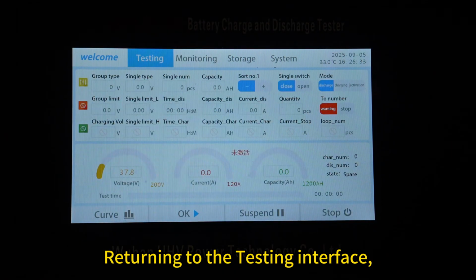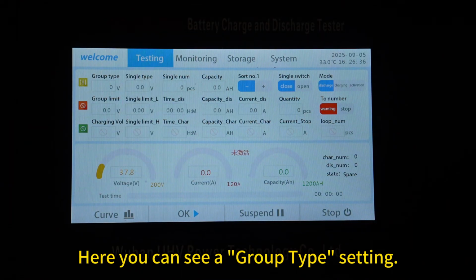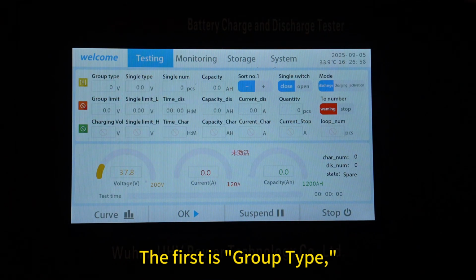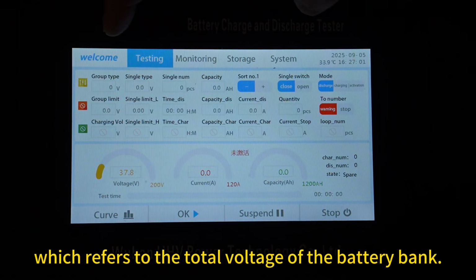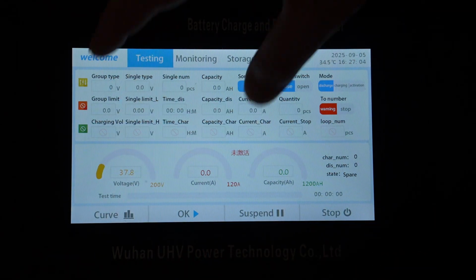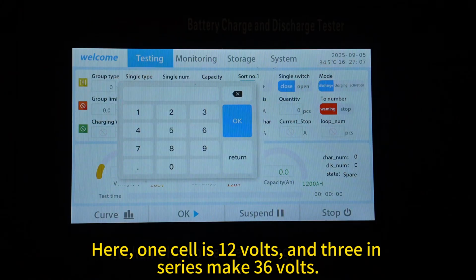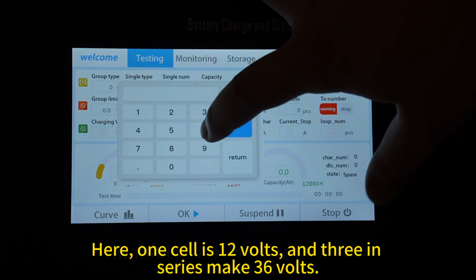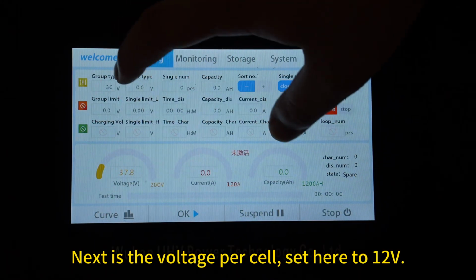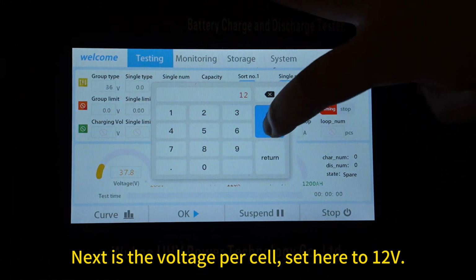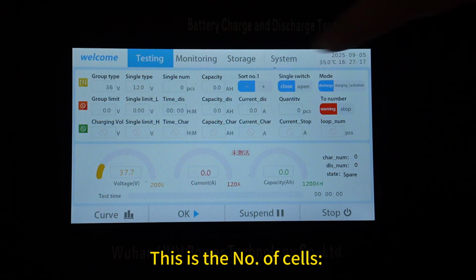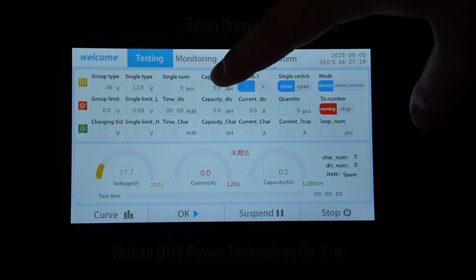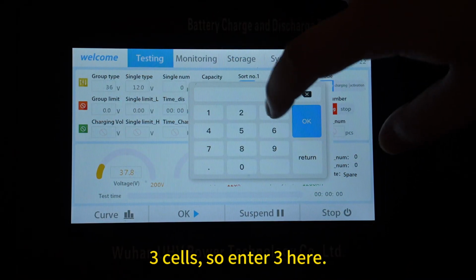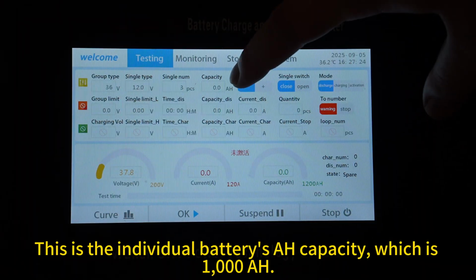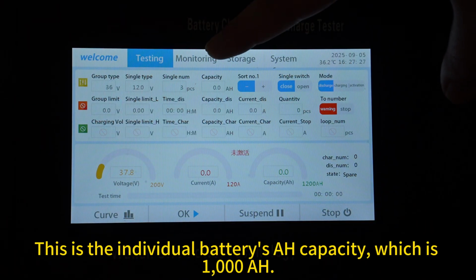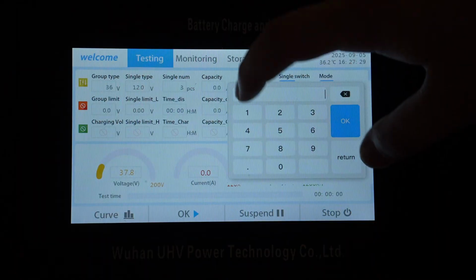Returning to the testing interface, here you can see a group type setting. The first is group type, which refers to the total voltage of the battery bank. Here, one cell is 12 volts, and 3 in series make 36 volts. Next is the voltage per cell, set here to 12 volts. This is the number of cells. 3 cells, so enter 3 here. This is the individual battery's ampere-hour capacity, which is 1000 ampere-hour.